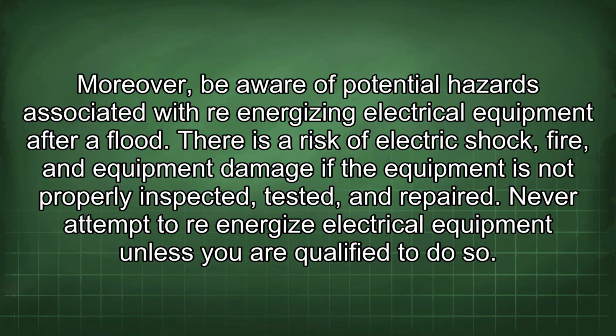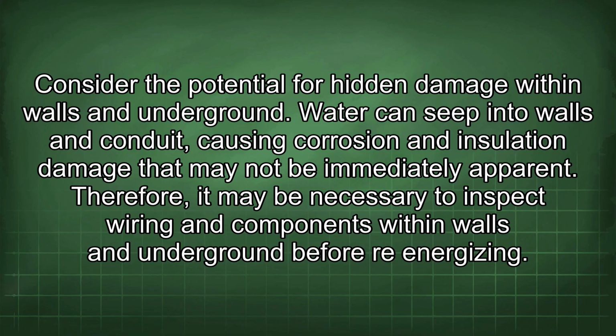Moreover, be aware of potential hazards associated with re-energizing electrical equipment after a flood. There is a risk of electric shock, fire, and equipment damage if the equipment is not properly inspected, tested, and repaired. Never attempt to re-energize electrical equipment unless you are qualified to do so. Consider the potential for hidden damage within walls and underground. Water can seep into walls and conduit, causing corrosion and insulation damage that may not be immediately apparent. Therefore, it may be necessary to inspect wiring and components within walls and underground before re-energizing.